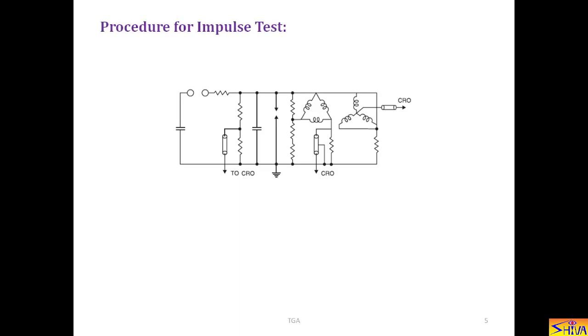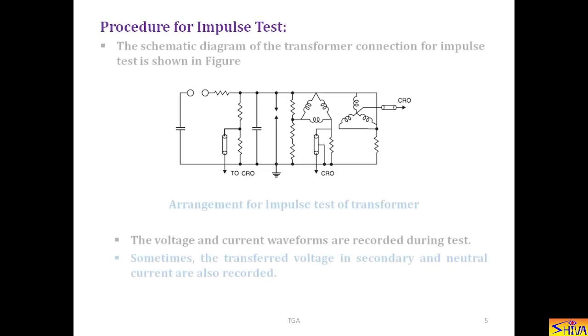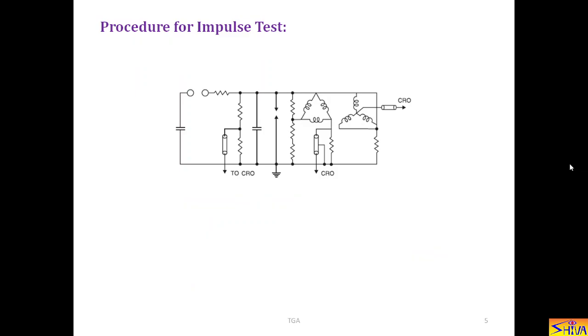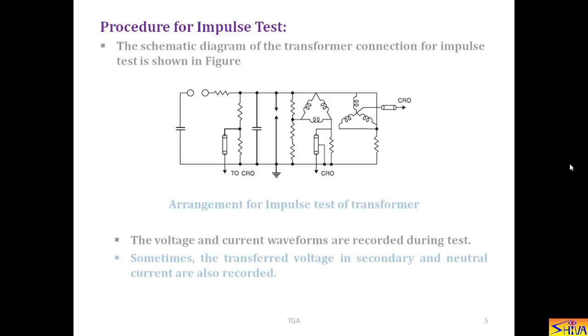Now, let us see what is the procedure for impulse test. The schematic diagram of the transformer connection for impulse test is shown in this figure. This is the transformer. Here it is the impulse generator output voltage shown in the form of capacitor. This is rod gap. It is triggered to apply the impulse voltage. This is potential divider. And this point is going to CRO. Low voltage arm of the potential divider is going to the CRO for recording of the impulse.